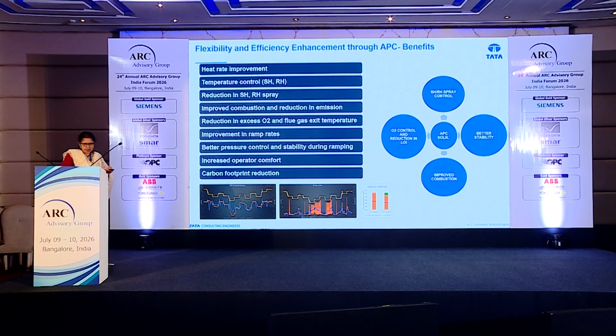These are the features implemented in APC: heat rate improvement, temperature control of the superheater and reheater, reduction in SH and RH spray, improved combustion and reduction in emissions, reduction of excess oxygen, and better pressure control and stability during ramping for increased operator comfort, which finally leads to carbon footprint reduction.